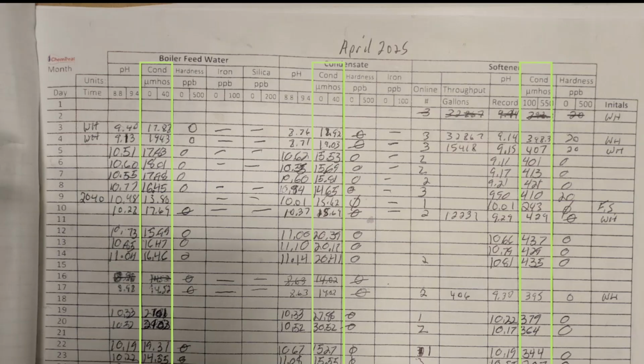Here's an example of a water treatment log. So here you have the boiler feed water conductivity. So boom, you have it right there. If you know the level that they're controlling to in the boiler, you can calculate blowdown percentage. Maybe you don't have that though. Maybe they're just showing you conductivity, and the outlet of your softener is your makeup water. You can see that it's much higher. So you're seeing readings in the 400s here as compared to in the teens here. So this particular facility has a good condensate return, and so the boiler feed water is a lot closer to the condensate conductivity than it is to the makeup water conductivity. But that can easily change with a change in condensate return percentage.